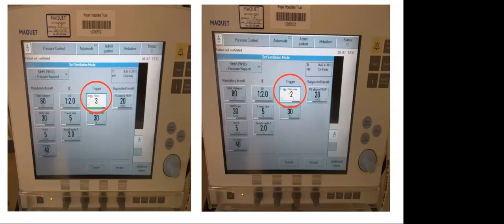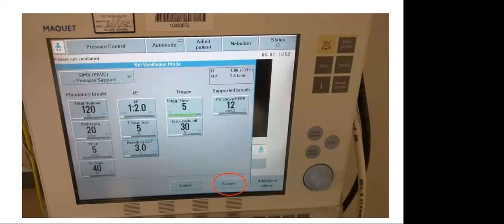What is the problem with a high flow trigger? If you have a ventilator circuit with secretions, that also will trigger a breath, so auto triggering is one of the common problems which can happen. Turning anti-clockwise reduces the flow trigger sensitivity, and it makes it harder for the patient to generate the flow needed to initiate the breath. Commonly the flow trigger is used. Pressure trigger we won't use because the patient has to create a negative pressure to trigger the breath. Start depending on the condition of the child again. Once you have set all the parameters, accept to confirm, and okay to confirm compliance and compensation.